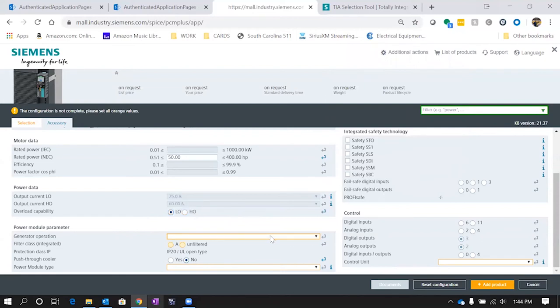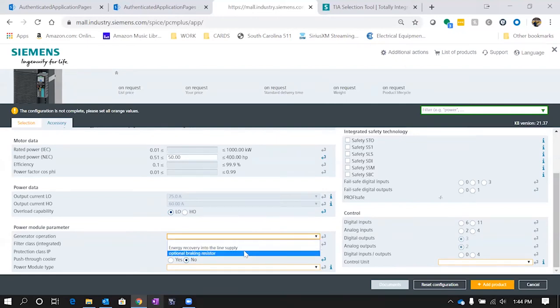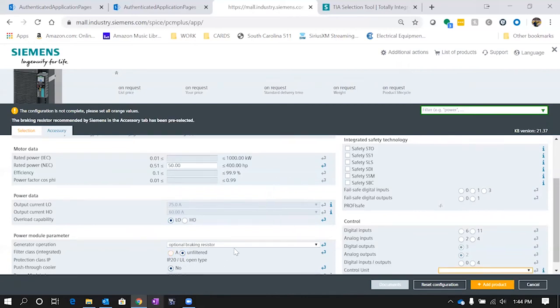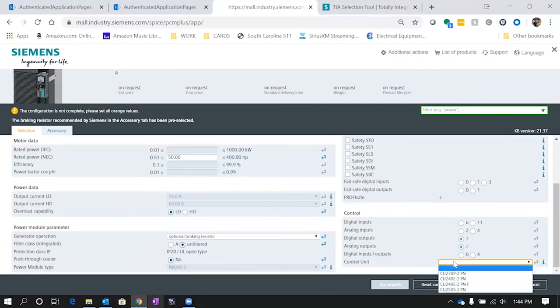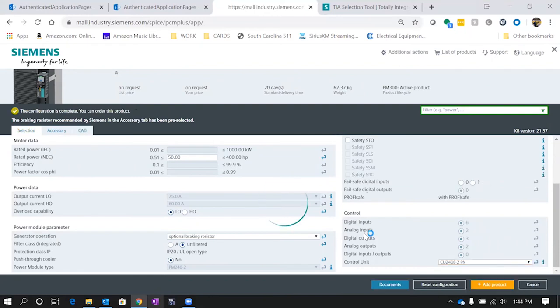Next we're going to select generator operation, whether we want to put energy back in the line supply, whether we want an optional braking resistor. We'll select optional braking resistor. Now we need to select filtered or unfiltered. Unfiltered is most common here in the United States. Last, we need to say what kind of control unit we want. The most common one is the CU240E-2, so we'll select that. Now you'll see configuration is complete. You can order this product.